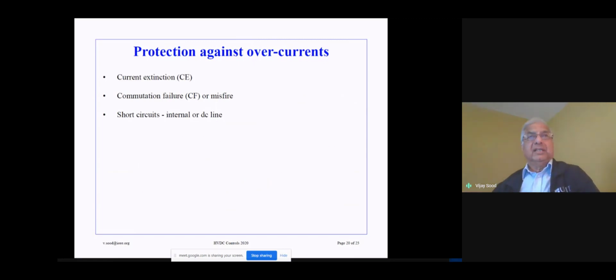So in order to protect against overcurrents, these are the three types of protection that we utilize. First is the current extinction, CE, a commutation failure or a misfire in the system, any short circuits internal or in the DC line. So we can protect against these kind of faults by using these control systems.